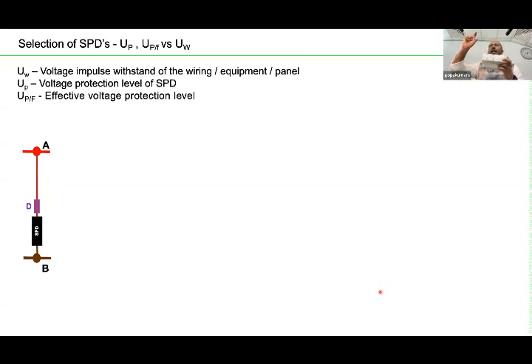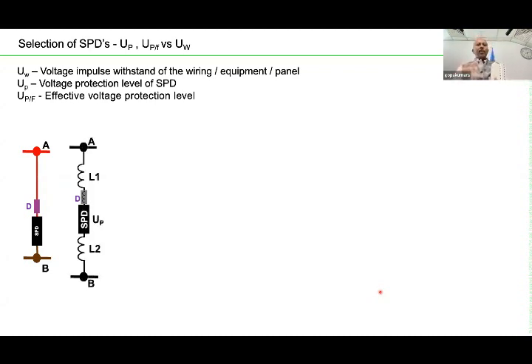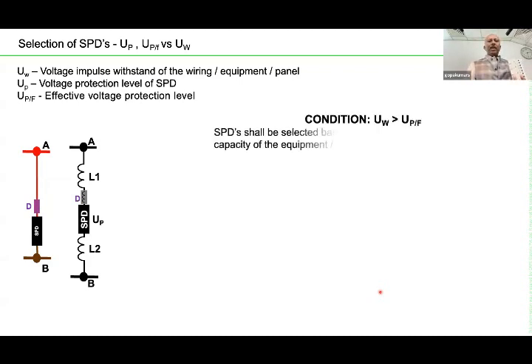HRC fuse or disconnecting device, because once the SPD fails, this device should isolate. As I said, all SPDs may create a short circuit, so you need an additional fuse to disconnect the SPD from the line. So imagine this is the way it is connected. Now what happens is, these connecting wires will offer certain impedance. It's not a short wire. Sometimes the wires are maybe 1 meter, 2 meters, sometimes 50 centimeters, the maximum recommended.